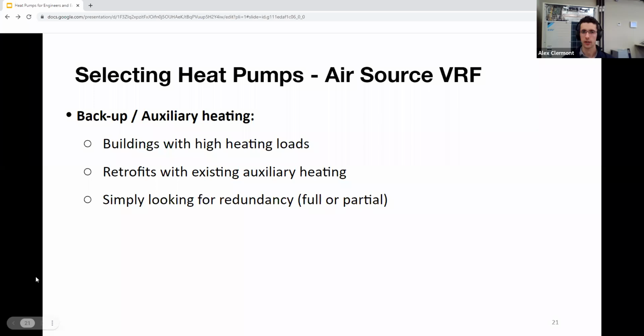Now, all that being said, let's say you are looking at an existing building and looking to retrofit it with heat pump technology. We've said this in the intro to heat pump module, but we always say it's best to look at your envelope before looking at applying heat pump technology. But that being said, let's say you do have an existing building with a high heating load. Does it make sense to go with cold climate models for the higher heating capacity, or should you use, let's say you have an existing auxiliary heat instead, does it make sense to use that source of heat? Again, it all depends a little bit on the building, but as previously mentioned, cold climate models will have the higher electrical draw. So in some cases where you have a limited electrical capacity, a new transformer, it might make sense to go with regular heating models and use electric heat to radiate hot water. Now, Jason's going to touch on a few different ways to do this in a little bit, but I just wanted to introduce that topic.